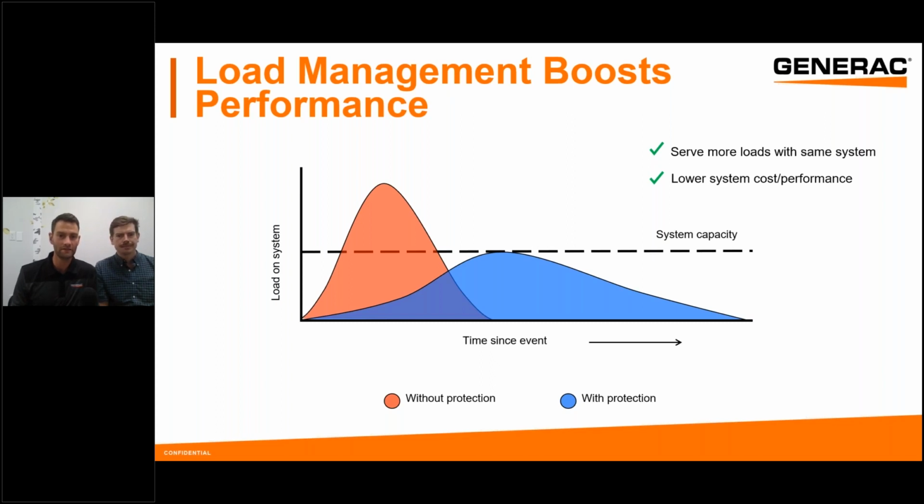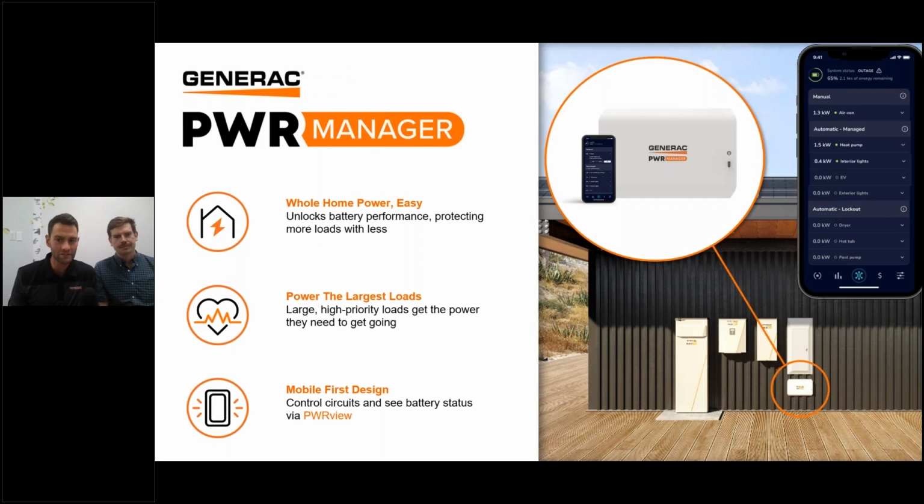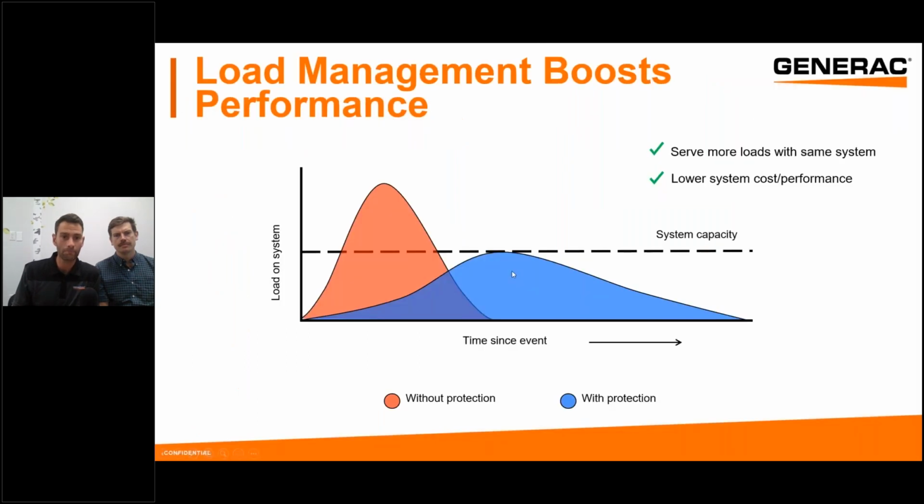Absolutely. I think as Jeremy said, the MSRP on this device is $1,000. So not only are we going to be thousands of dollars less than some of the other hardware out there, but it installs in about 2 hours. If you're curious, you're just extending circuits from the panel through these relays and then back into their breaker. And the programming is quite simple too. We have videos on the commissioning and install of this device already on our Clean Energy YouTube page, which I highly recommend you check out.